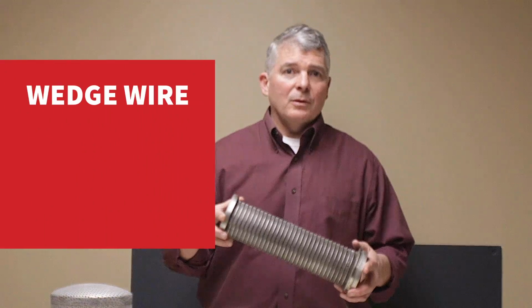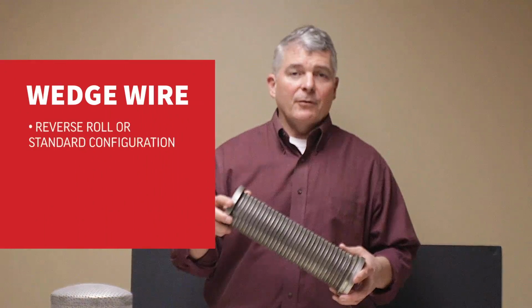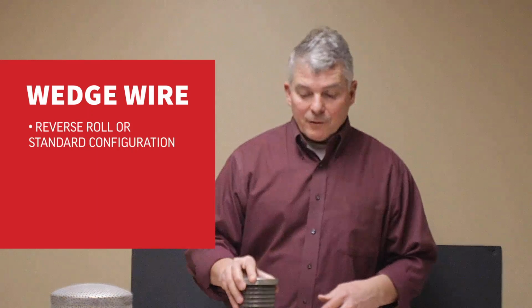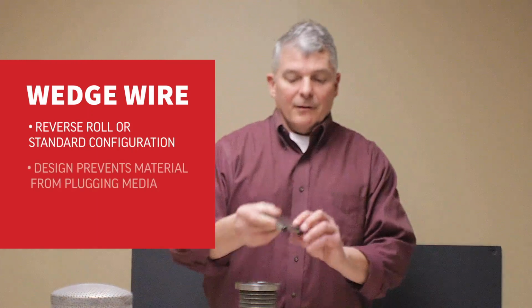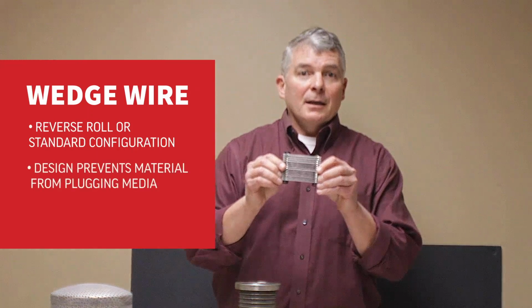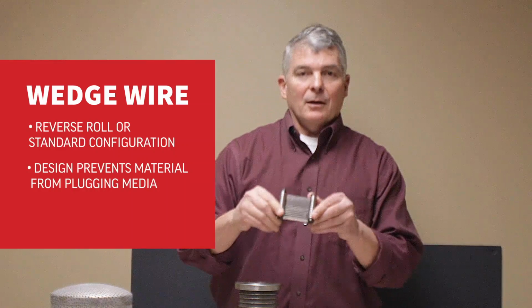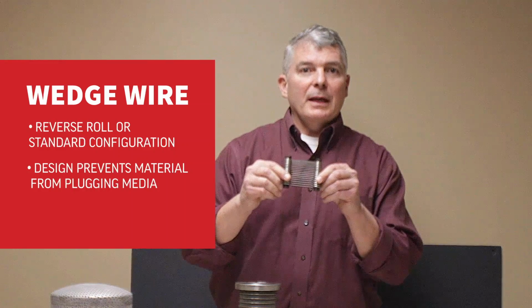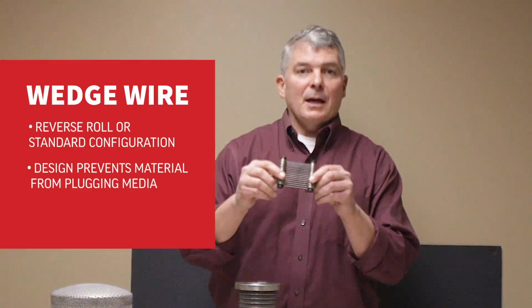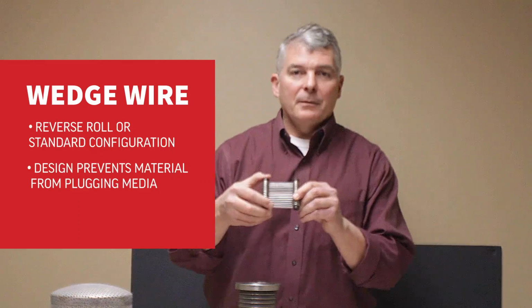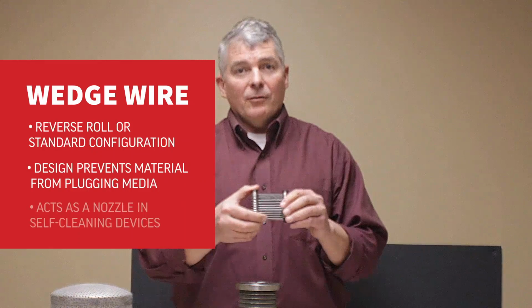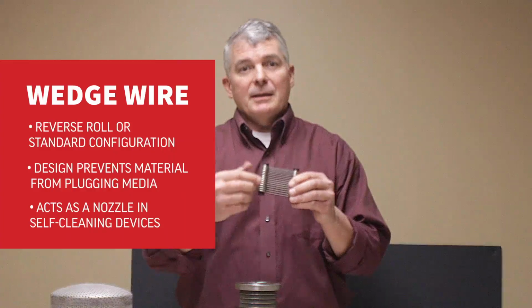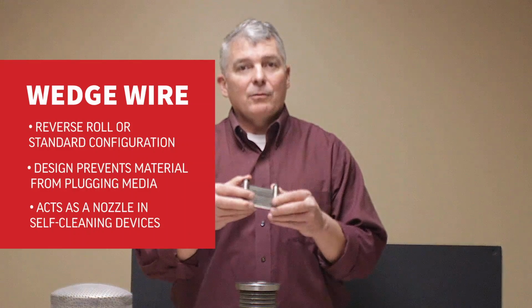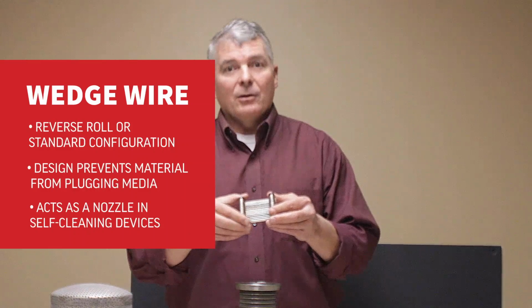We have wedge wire, both reverse roll as well as standard configuration. What the wedge wire offers is a defined slot on the dirty side and a large opening on the back side so that anything that does get through that slot opening will not plug the media. It also helps in a self-cleaning configuration because it acts as a nozzle when the water flows back through that angled area.